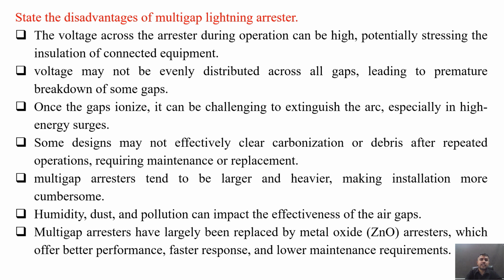State the disadvantages of multi-gap lightning arrestors. So there are several disadvantages of multi-gap lightning arrestor. The voltage across the arrestor during operation can be high, potentially stressing the insulation of connected equipment. Voltage may not be evenly distributed across all gaps, leading to premature breakdown of some gaps. Once the gaps ionize, it can be challenging to extinguish the arc, especially in high energy surges.